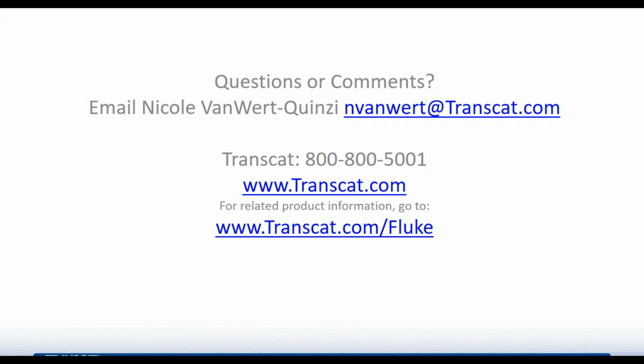Okay, the next one is more of a statement than a question, but maybe you can comment on this. He says, I have trouble with wet calibrations on transmitters used on water. Oh, yeah, and with the liquid calibration, you have a couple options. If you want to use air, you need to isolate the transmitter from the line that's coming in.